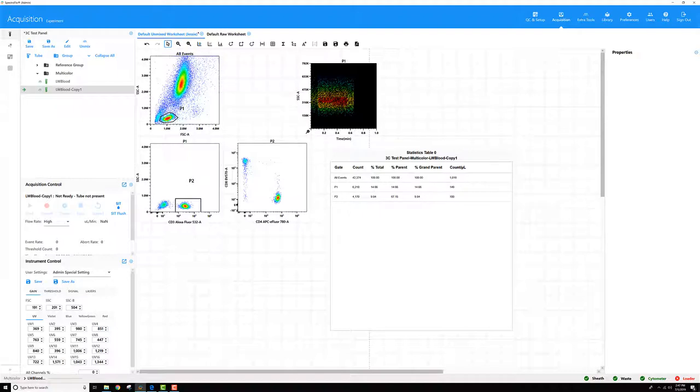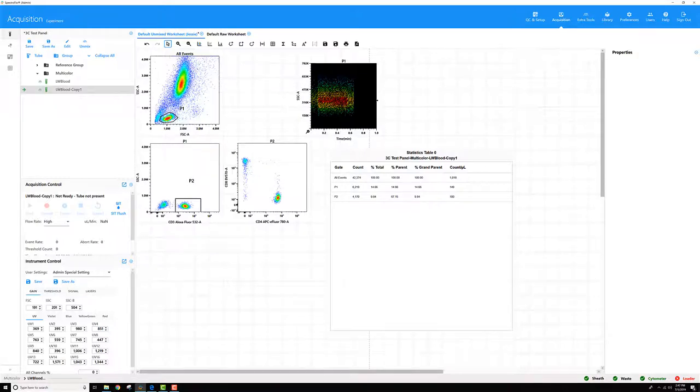What you're looking for is you want to make sure that the pattern is relatively smooth from start to end. If you see any parts during the acquisition where the density of events decreases sharply or if there's a gap because an air bubble went through, you're going to want to exclude that data. You're not going to get a very accurate count if things like that happen during acquisition.